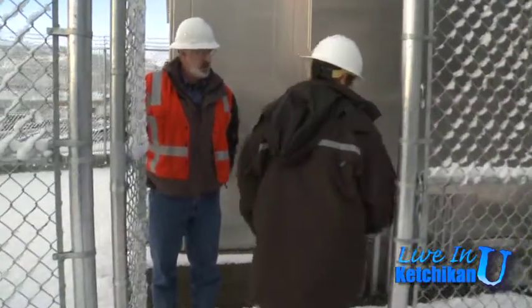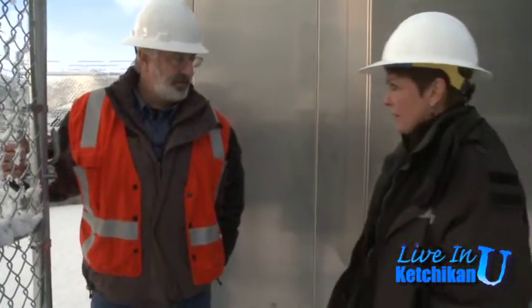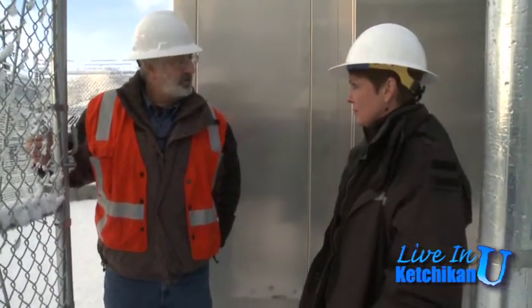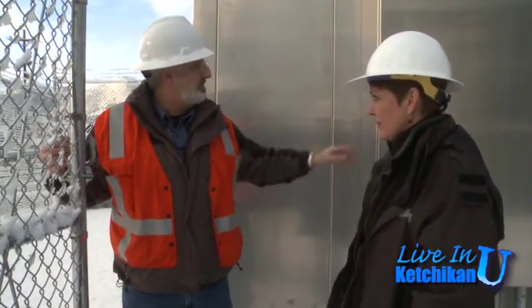So the one thing we have to consider while we're in an active substation is something called the MAD, the minimum approach distance. That's 10 feet to an energized part. So if you don't know to recognize energized parts, stay close to me and I'll identify them for you. We'll go into the power control building.